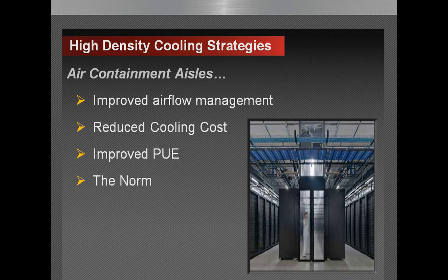So hot aisle, cold aisle configurations, which has been the industry standard, is no longer a viable solution as power densities have significantly increased, outpacing improvements in HVAC technology. Air containment aisles improve airflow management within a data center by focusing cooling to the more narrow scope of cooling individual components, as opposed to the wider scope of cooling the entire room. This cooling technique has been proven efficient and effective at reducing cooling cost, and today is really the norm.